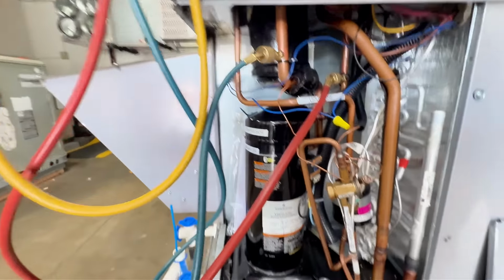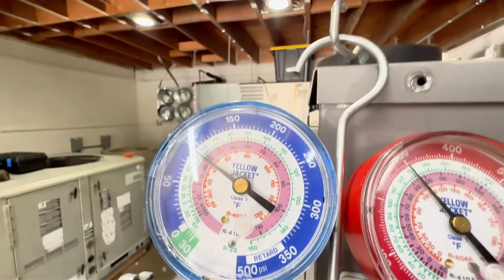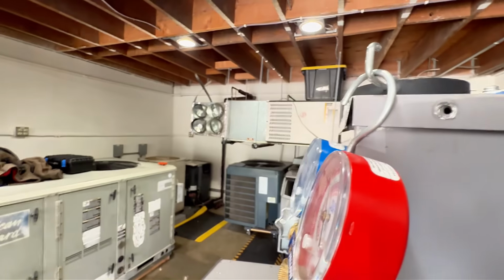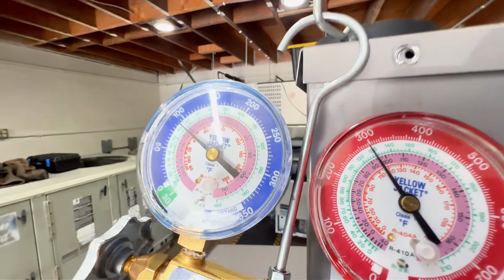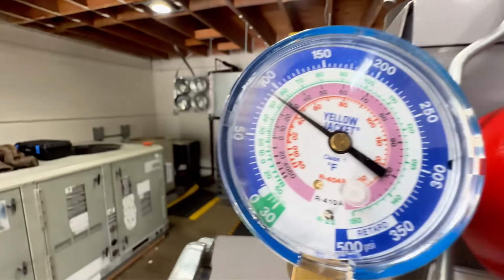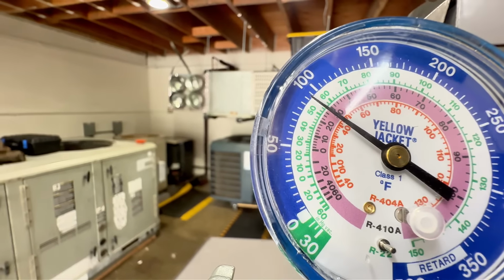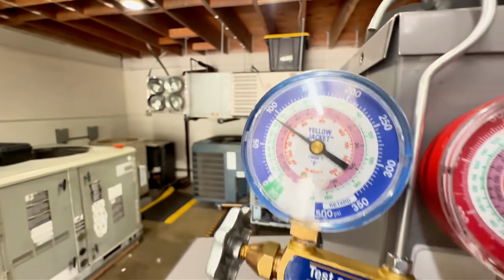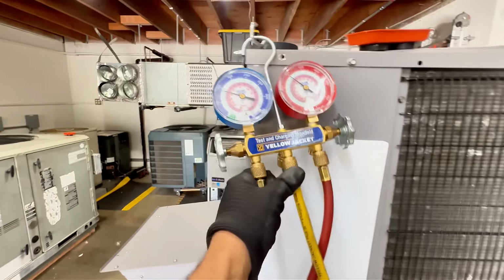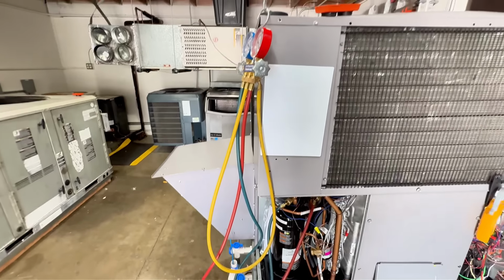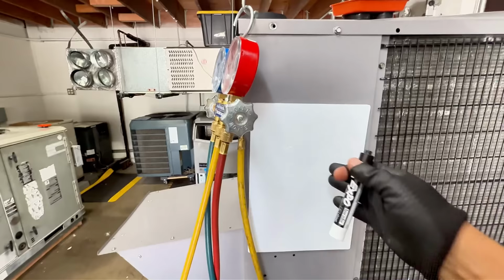Okay. Now, let's go ahead and get our pressures. This is a 410A. So right now, I'm almost close to 300 PSI. 300 PSI. Let's go ahead and show you that, right? 300 PSI. And that one's close to, man, it's 90 PSI. So I don't know if it has a refrigerant issue. Right now, we're going to get all of our numbers. And you'll be able to determine what's going on by looking at numbers.